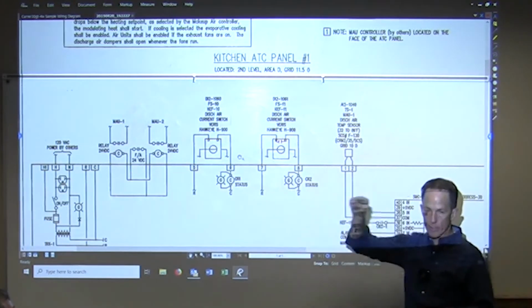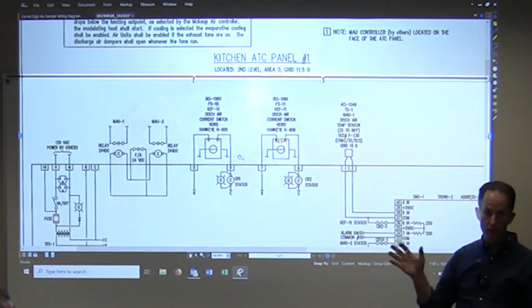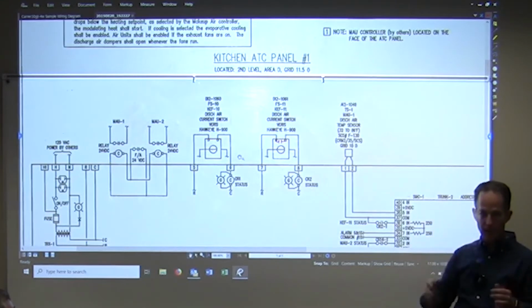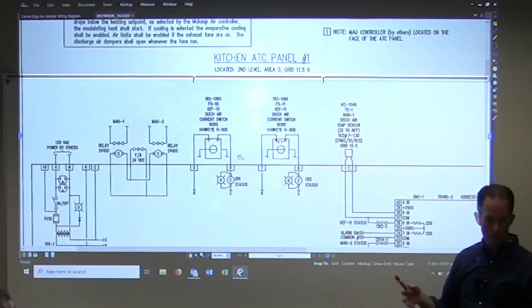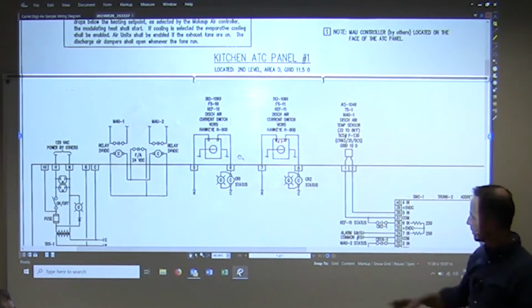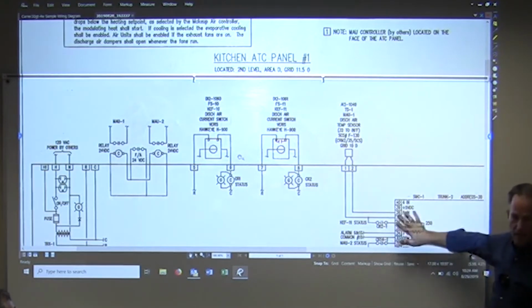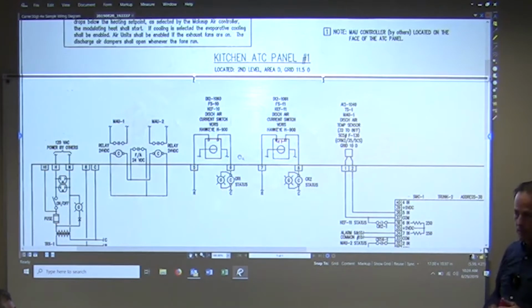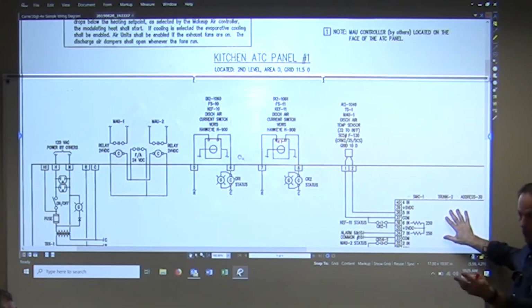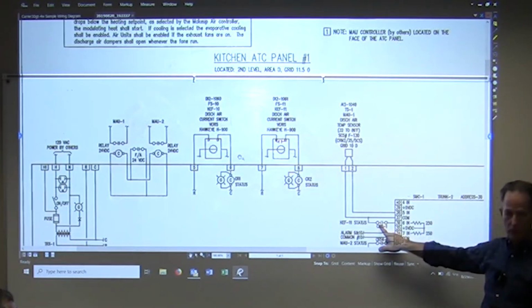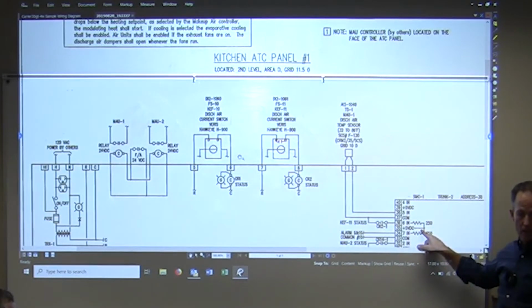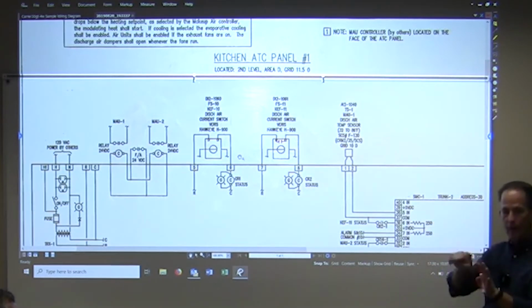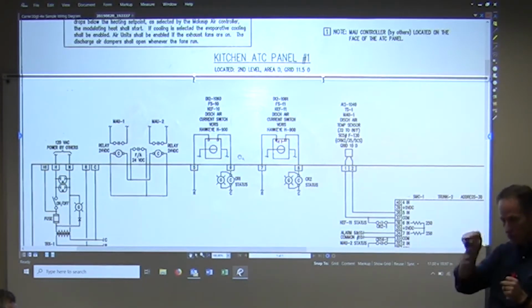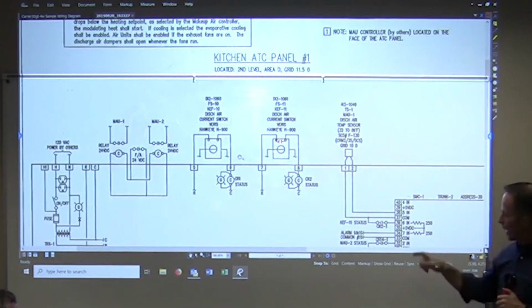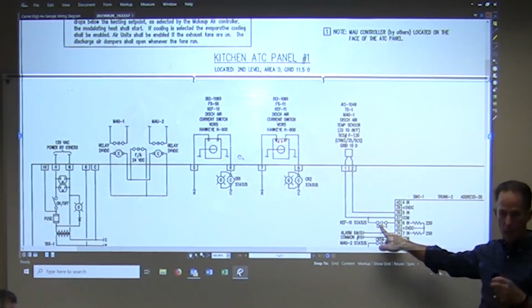Now, this doesn't have the little 2P, 3P, 4P up next to it like some do. Not all do, but that tells us how many poles or how many sets of contacts, right? In this case, we assume it's at least one. It's probably two because that's a lot of times the ones that we use. But one of those goes here. And what is this telling us? What is this doing here? It's input to the card, provide a status on DDC. Okay, so we have our controller, our card that's collecting information. Because it's a closed contact, it's a status into the controller. So these little resistors that you see underneath, or on the inside, those are wired in at the base. So if I pulled the card off of the base, you would see a resistor put in between those terminals. And it's used to work with that particular contact to make it work for the controller.